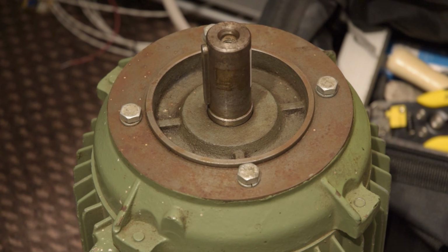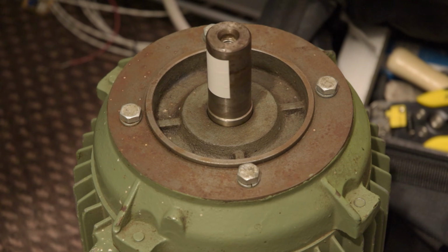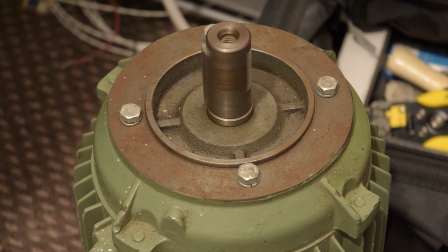If I press the button to turn on the output, you can see the shaft starts to turn, which is quite nice, and right now it's spinning nice and slow. I still have speed control, so I can turn up the speed like this, and continue to turn it up. This motor's designed for operation on a 50 Hz 3-phase supply, but because I'm making my own 3-phase supply, I can spin it as fast as I want, really.